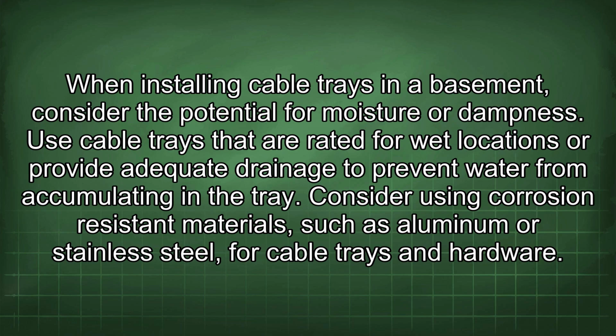When installing cable trays in a basement, consider the potential for moisture or dampness. Use cable trays that are rated for wet locations or provide adequate drainage to prevent water from accumulating in the tray. Consider using corrosion-resistant materials, such as aluminum or stainless steel, for cable trays and hardware.